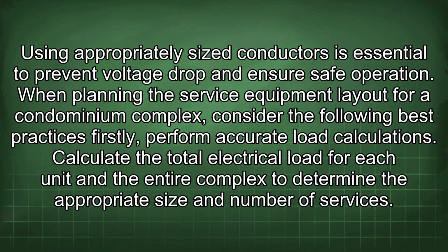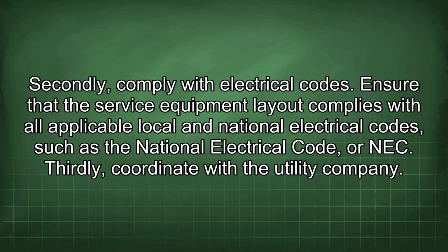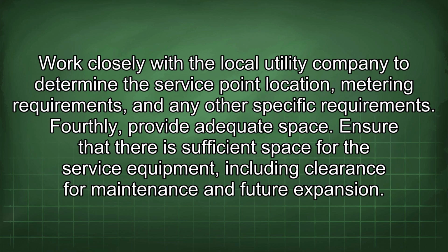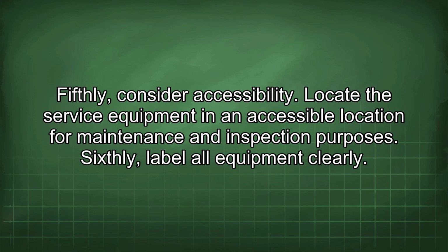When planning the service equipment layout for a condominium complex, consider the following best practices. Firstly, perform accurate load calculations. Calculate the total electrical load for each unit and the entire complex to determine the appropriate size and number of services. Secondly, comply with electrical codes. Ensure that the service equipment layout complies with all applicable local and national electrical codes, such as the National Electrical Code, or NEC. Thirdly, coordinate with the utility company. Work closely with the local utility company to determine the service point location, metering requirements, and any other specific requirements. Fourthly, provide adequate space. Ensure that there is sufficient space for the service equipment, including clearance for maintenance and future expansion. Fifthly, consider accessibility. Locate the service equipment in an accessible location for maintenance and inspection purposes.